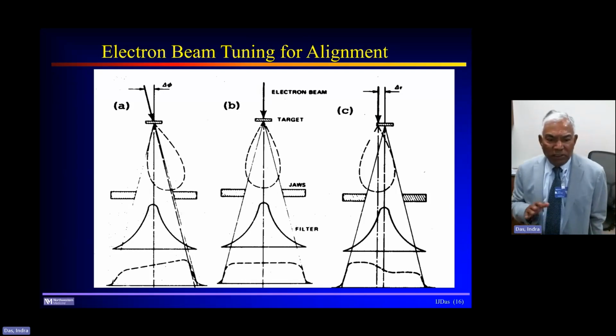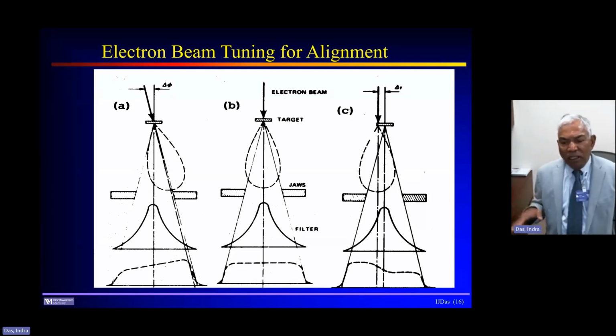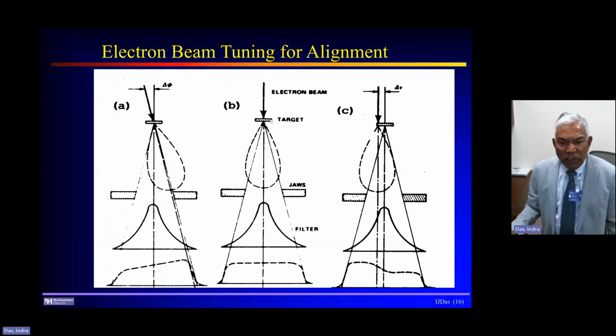When engineers are assigned to your machines, when they come in the house, they tweak your beam parameters. Imagine if the fellow didn't pay attention, and he let the electron beam go at an angle, you will have asymmetry. This is a perfect scenario when the beam is exactly coming on the center, and with the flattening filter, you can see that the beam is flat.